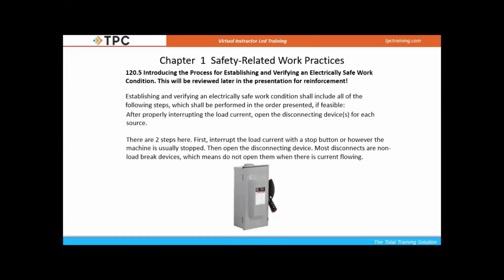Secondly, there are two steps to this requirement. It says after properly interrupting the load current. What does that mean? It means we go hit a stop button, or open an interlock or whatever, to get no current flowing through this disconnect, or the circuit breakers, or whatever we have that can de-energize the circuit.